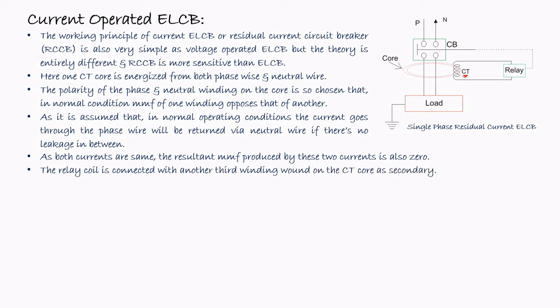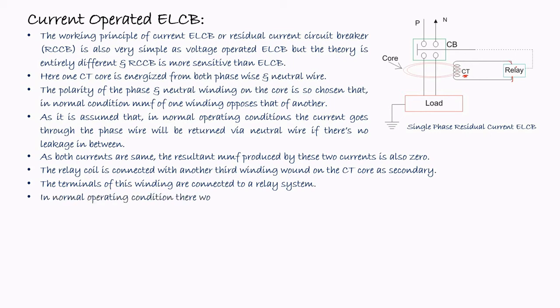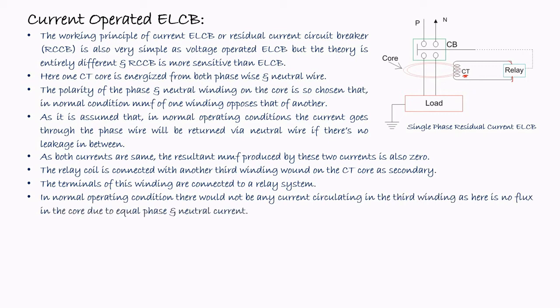And the relay coil is connected with another, third winding wound on the CT core as the secondary. So here it is shown the relay is connected with the CT. It is considered as the secondary winding. The terminals of this winding are connected to a relay system. In normal operating condition, there will be no current circulating in the third winding as there is no flux in the core due to equal phase and neutral current. So in normal working condition, there will be no current flowing in this path. So the relay will not be activated and the RCCB will not trip.